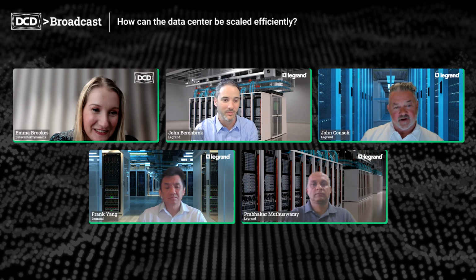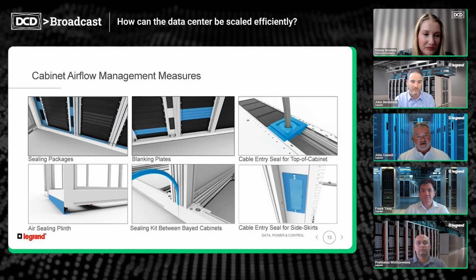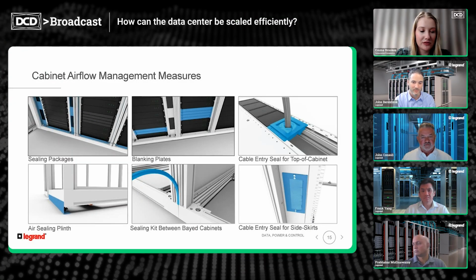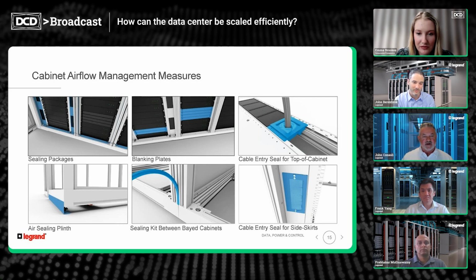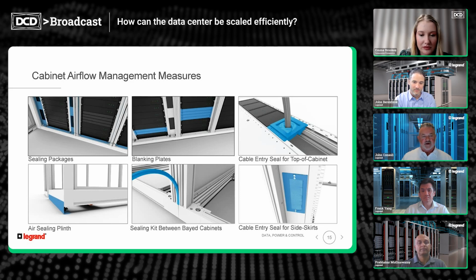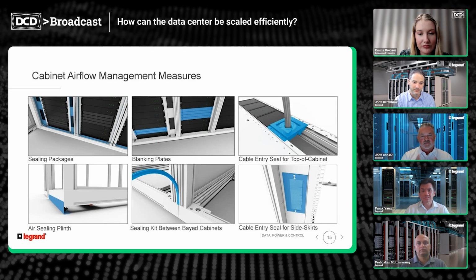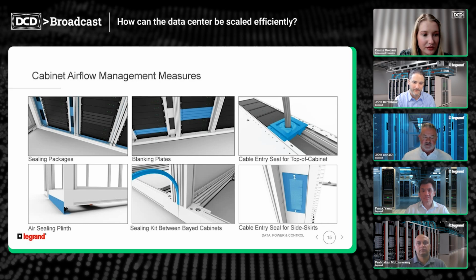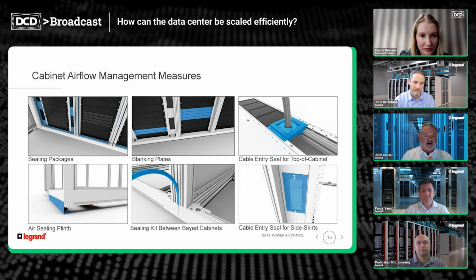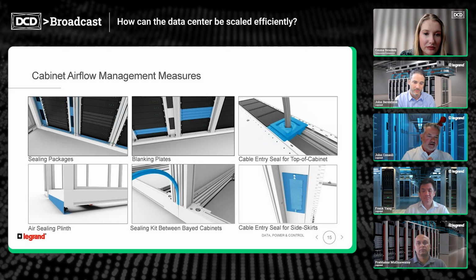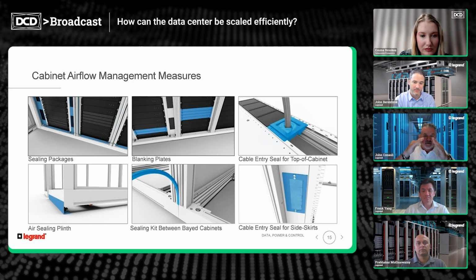Emma, thanks for that question. The things that get overlooked are attention to detail. With the amount of airflow moving through these cabinets, it's really important to be more diligent than ever in sealing any possible place where air could leak out of the cabinet. We recommend, whether it's a Legrand rack or not, that the best test results come with a rack or cabinet frame that is fully welded, because when two pieces are properly welded together, there's no leakage that can occur.